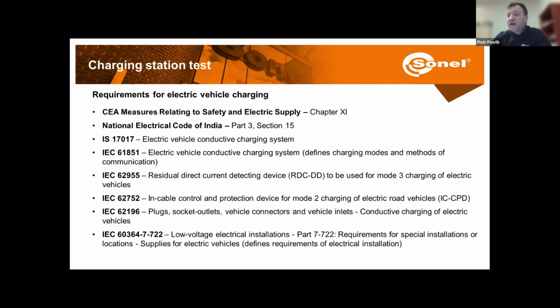And further on, we have the international standards, like IEC 61851, which describes the modes and methods of communication. Then we have IEC 62955 and 62752, which describe the residual current devices. Plugs, sockets, and connectors: this is IEC 62196. And IEC 60364, where Part 7-722 describes the requirements for special installations that supply electric vehicles.